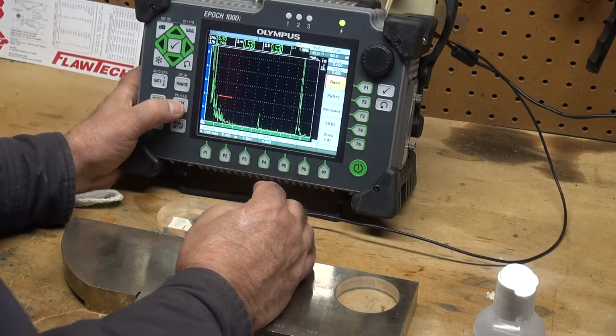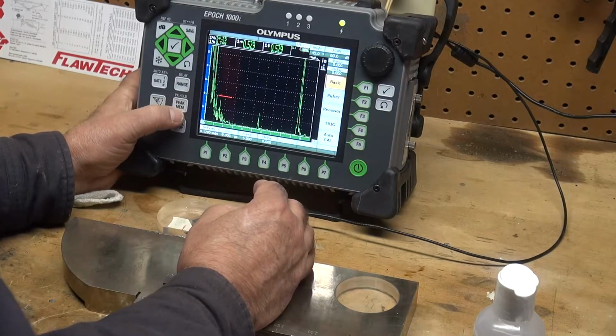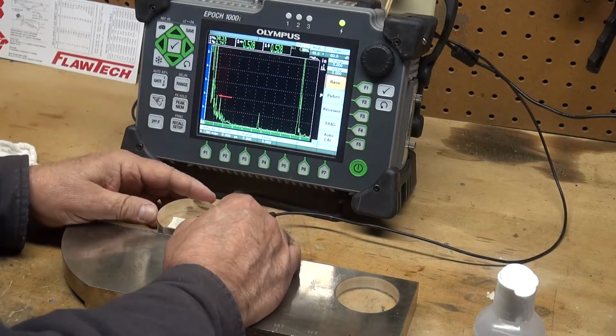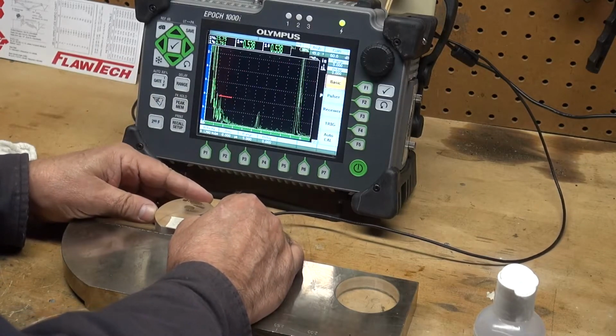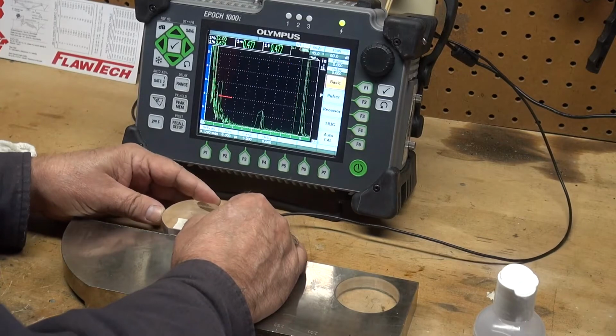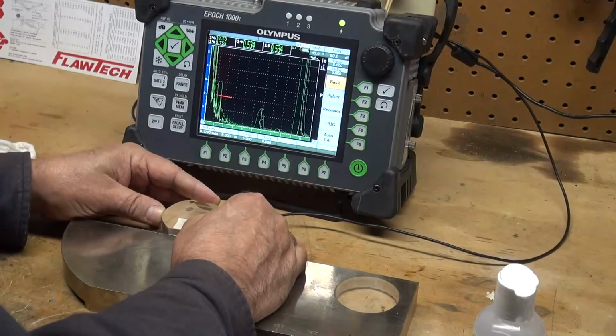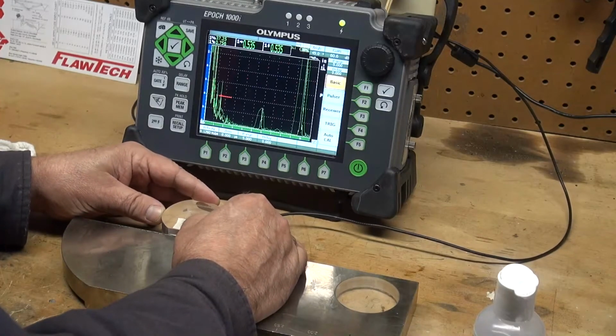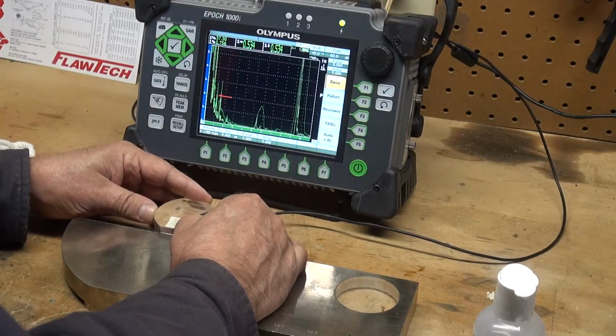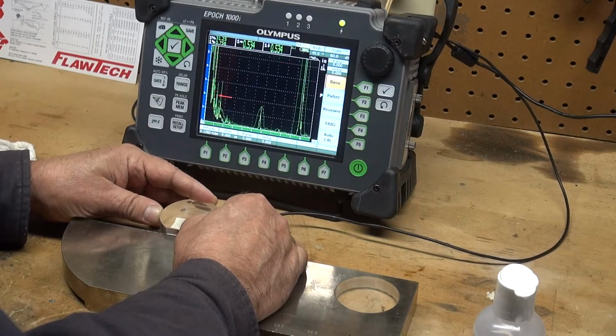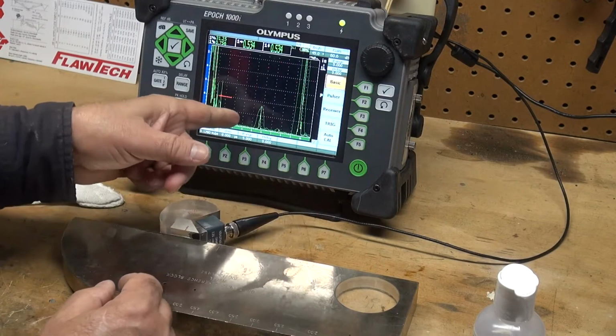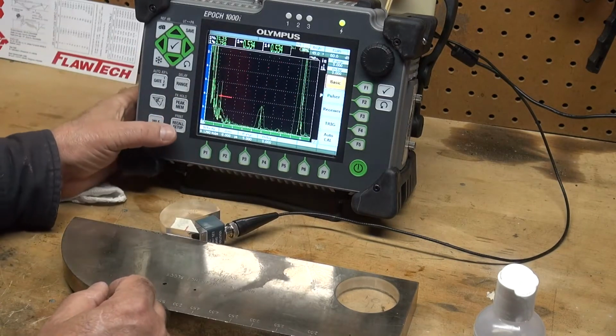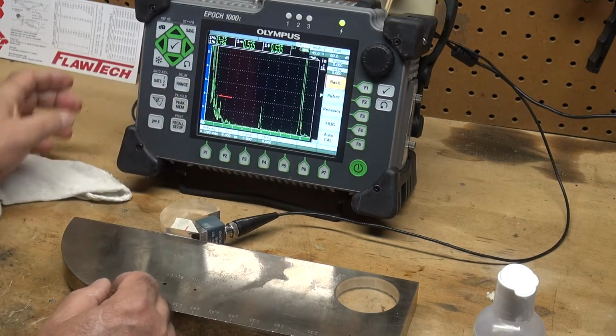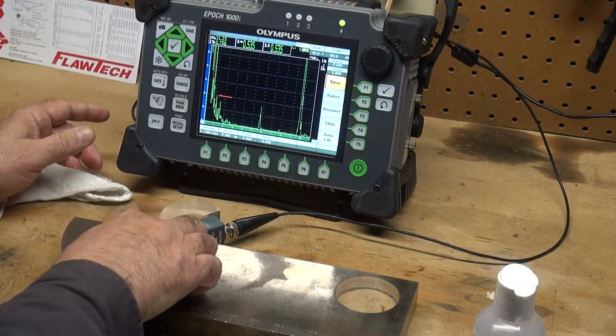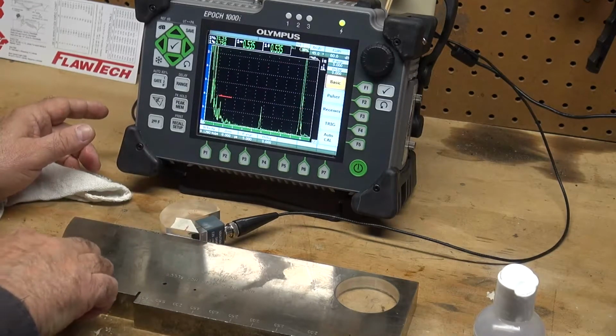Now the Olympus EPOCH 1000i has a peak memory. What I'm going to do is just move back and forth, and you can see the trace is remembered there, how it shows that trace. I'm going to peak right in the center of that curve. That is my beam index point. That is where the maximum energy is coming back from this radius.